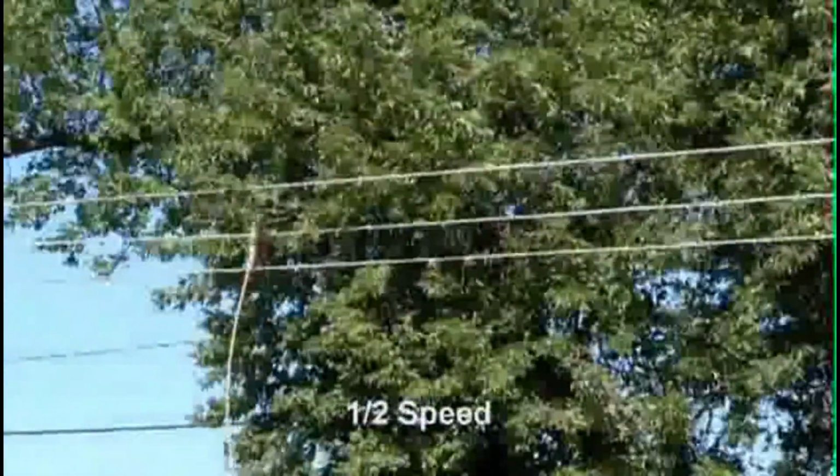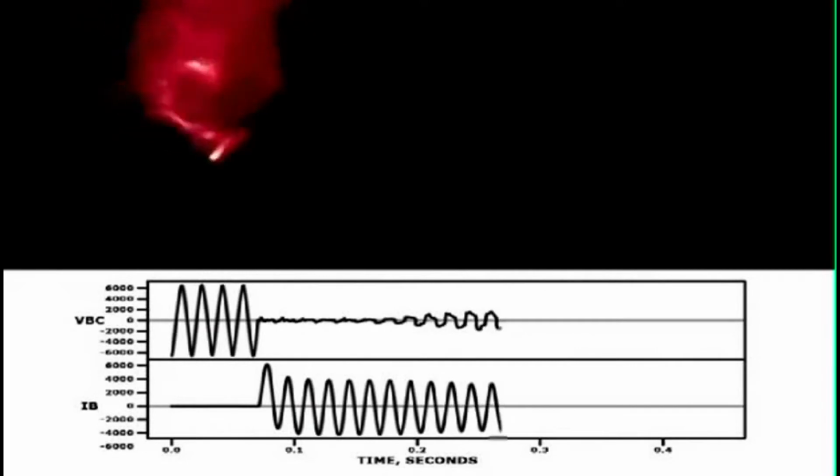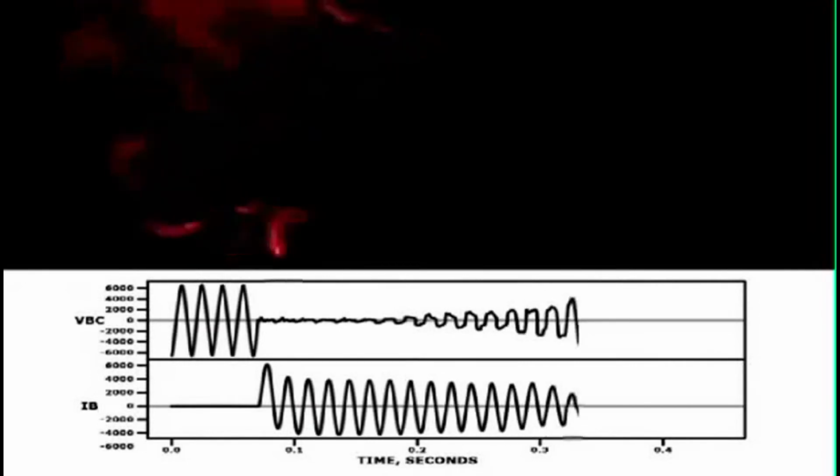Does it swing away? And we found pretty quickly that the arc wants to get big pretty fast. That lead will drop away and the arc can really make a pretty long arc. That's more of a safety hazard for the worker. The incident energy that might hit a worker is a function of the energy in the arc. So we know the voltage and the current, we know the power, we know the duration. Then we also have some high-speed cameras, so we see where the arc goes. We want to know where the blast goes relative to where a worker might be in various scenarios.